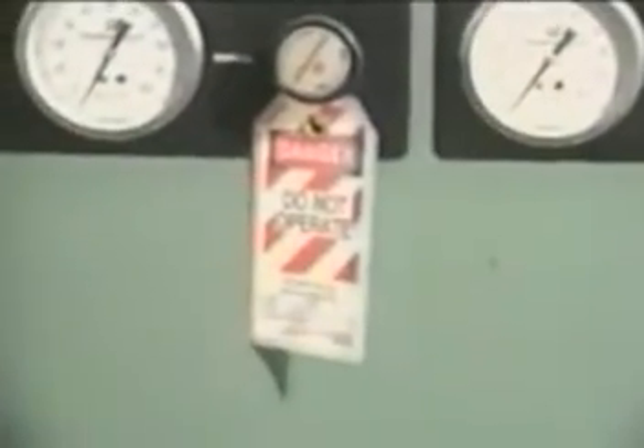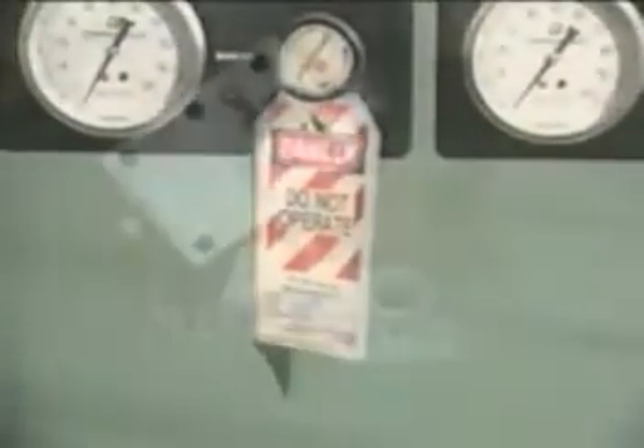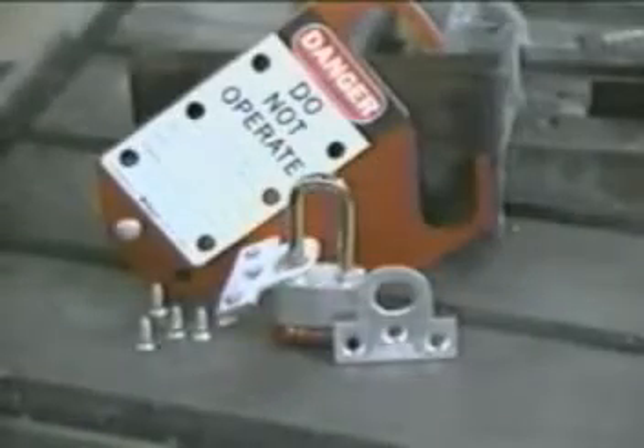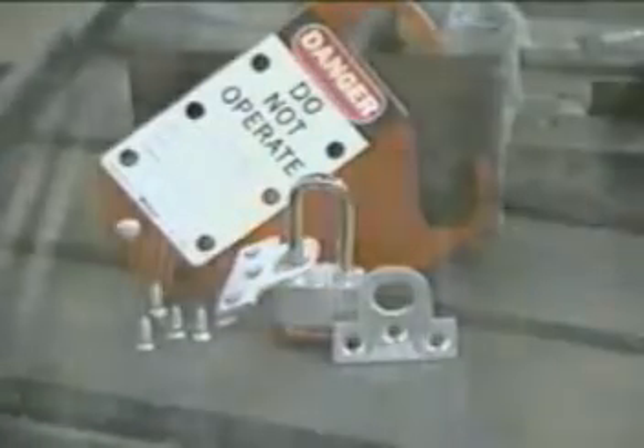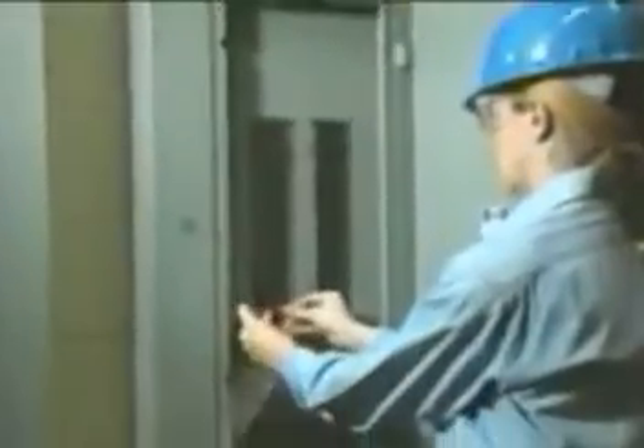If your employer requires only the use of tags, you must place them at the same point where locks would be attached. A tag should clearly indicate that removing it and reactivating the flow of energy is absolutely prohibited. For equipment that is incapable of lock attachment, place a tag as close to the energy isolating device as possible, or attach padlock eyes to the mechanism and affix your lock. The following devices will be helpful in various energy sources.